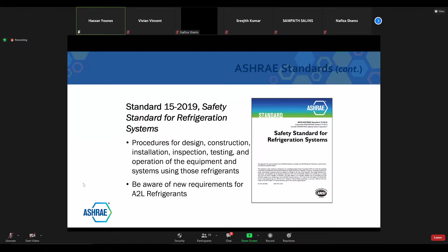Even if you have a normal, simple DX split unit, you need to look at the concentration in the room, because if there's any leakage in the room, that high pressure refrigerant can push the air from the room to the outside, and then that could suffocate people on the inside. So it's very important to look at the standard when you are designing anything that has refrigerant inside, especially refrigerant that is in occupied zones.